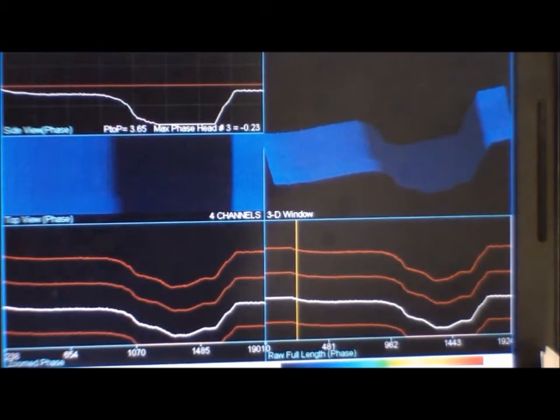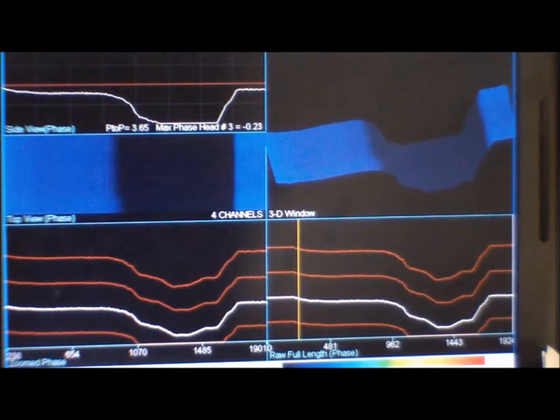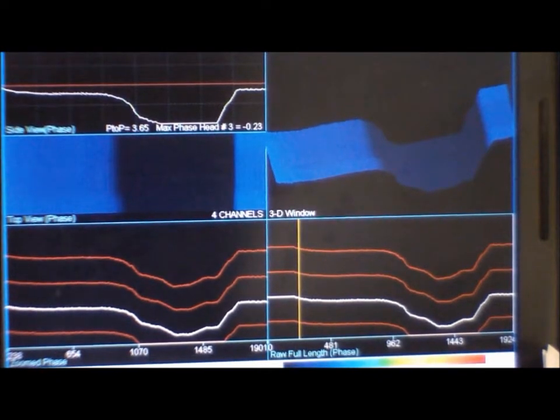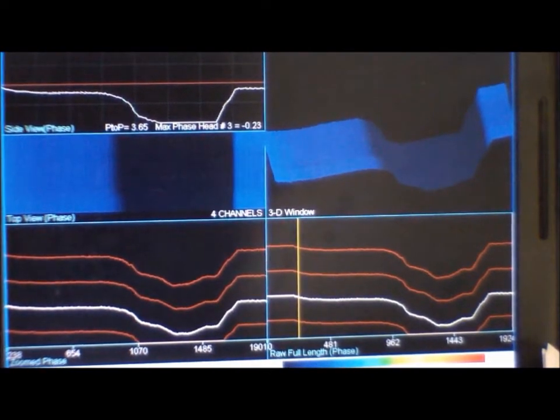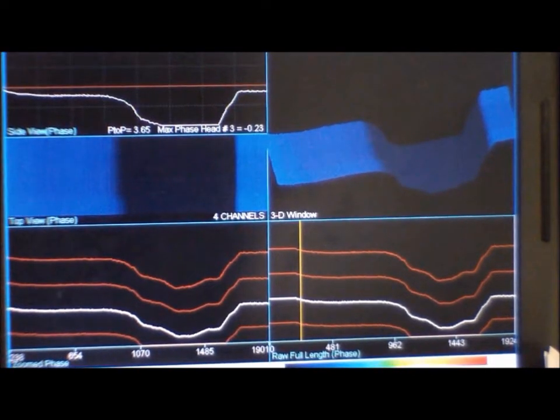This screen shows the data in our analysis program. The scanner contains four pickup sensors which are represented by the four lines of data. The drop in the waveform is where the scanner went over the 50% deposit of magnetite.